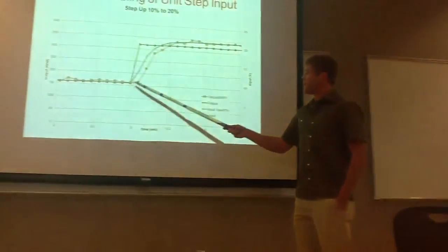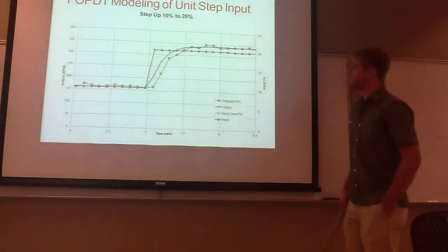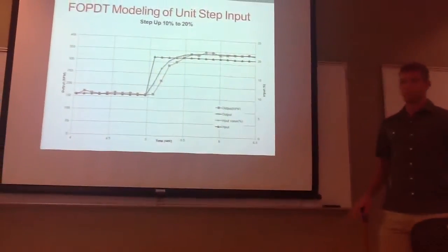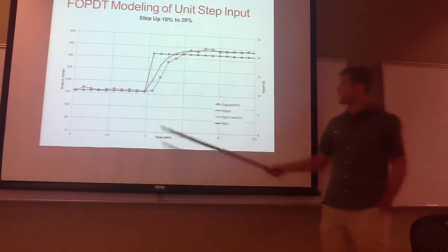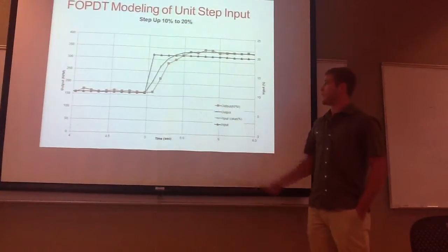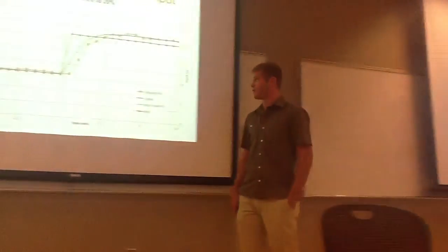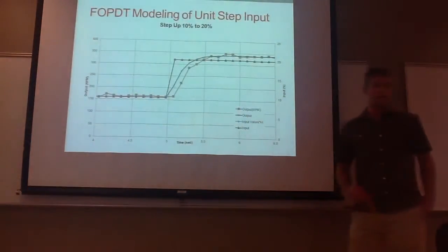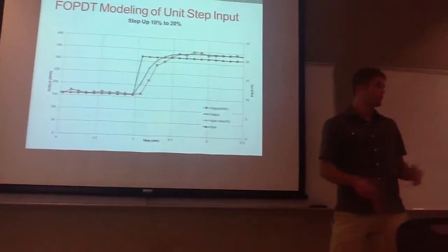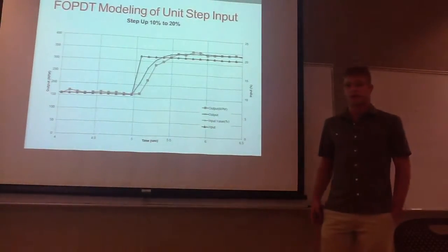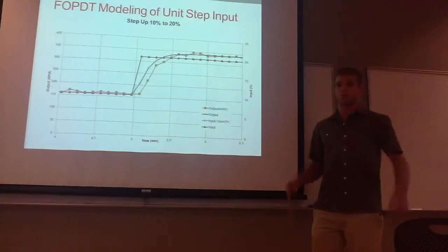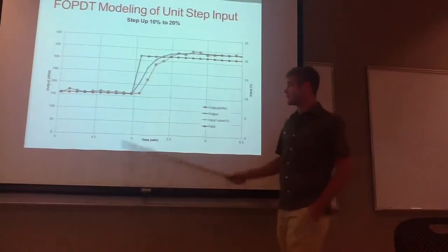We were then tasked with fitting the FOPDT model to the actual experimental data. The purpose of the FOPDT model, like the steady-state operating curve, would be to predict the actual behavior of what the motor should see, assuming no sort of resistance or external inhibitors to the actual performance of the aeration system.